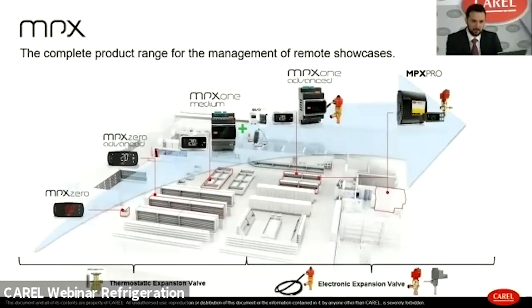In the entry-level segment we have the MPXzero series up to the MPXone Medium. The MPXone Medium, even if designed for entry-level applications using thermostatic or solenoid valves, can be upgraded to manage electronic expansion valves through an external driver EVD IS or EVD Mini. For applications requiring high-efficiency performance and built-in management of electronic expansion valves, the offer includes the MPXone Advanced and the MPX Pro.